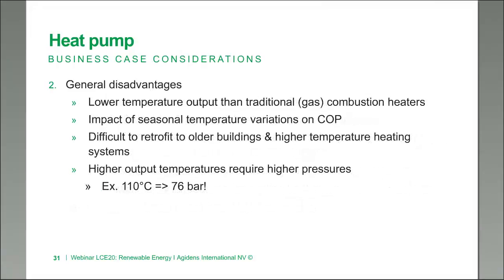Of course it's not all good — in some cases there are disadvantages to heat pumps as well. A lot of times heat pumps can only provide lower temperatures than what a traditional gas combustion heater can provide. In case you're using a temperature source which has seasonal impact, you'll see a seasonal impact on your COP — the seasonal performance factor will determine your real efficiency. Very important also is that retrofitting the heat pump to older buildings or older installations may not always be easy, since these installations will often have been designed for higher temperature systems, and it may not always be possible to reach the performance level users expect.